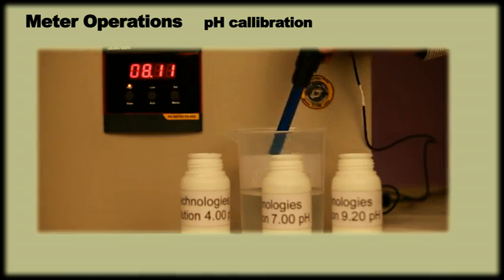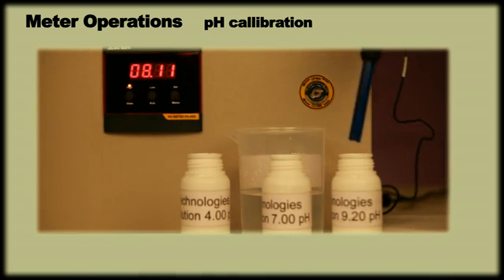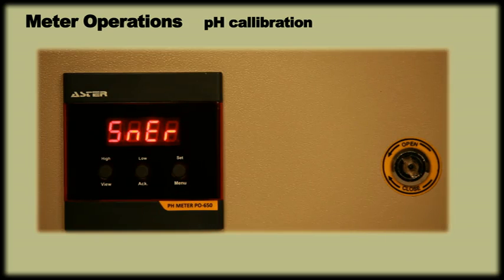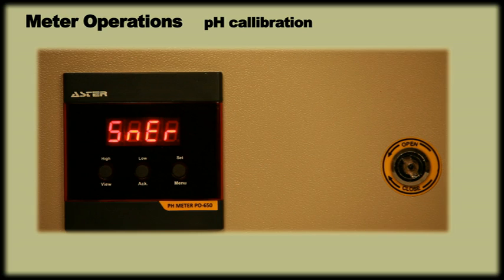In order to cross check the calibration settings, the meter has a third point checking facility. Please note that if the actual reading for 0 and span differ by 40%, then the meter will show sensor error and start showing readings as per previous calibration.